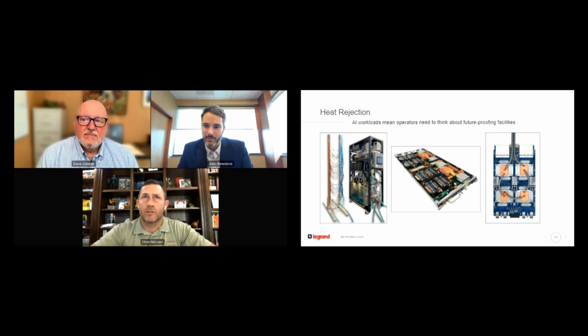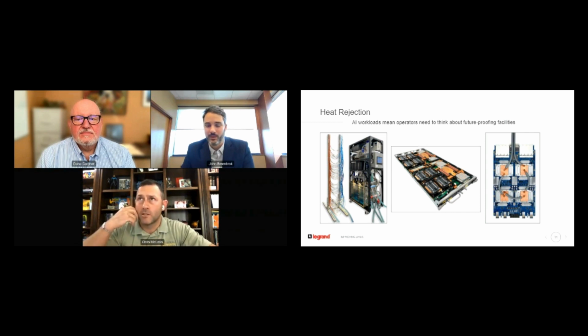It's a great question, and I'm working through it on 3 projects right now, where you're either going to have to bring secondary PDUs or receptacles into your cabinet to pick up the CDUs, or you're plugging into your critical power PDUs and you're putting those pumps directly onto the critical bus the way that you described. And the interesting thing is that it shifts your PUE. It shifts some pump load and some pump energy from the mechanical side of the system to the critical side of the system, which depending on the efficiency of the system, could be good from an energy standpoint.